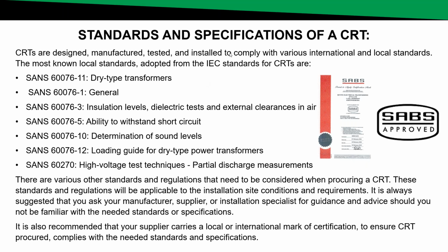Let's have a look at the relevant standards and specification for cast resin transformers. Cast resin transformers are designed, manufactured, tested and installed to comply to various local and international standards. The most common local standards adopted from the IEC are listed on the screen. The most important one for me that needs to be considered is the SANS 60076-11 for dry type transformers. In this standard, all the relevant requirements and parameters for manufacturing, designing, and testing of dry type transformers are mentioned.